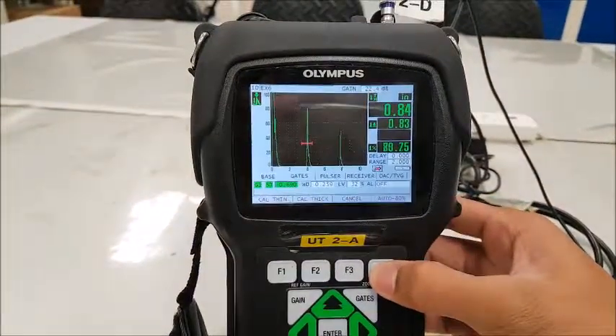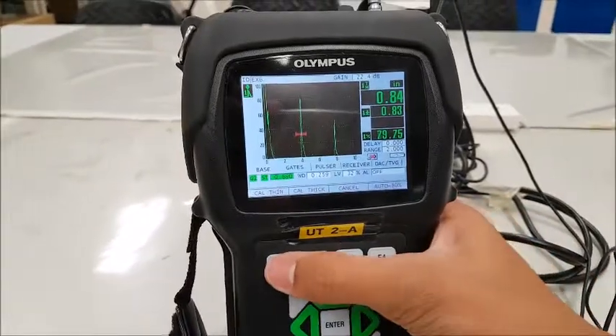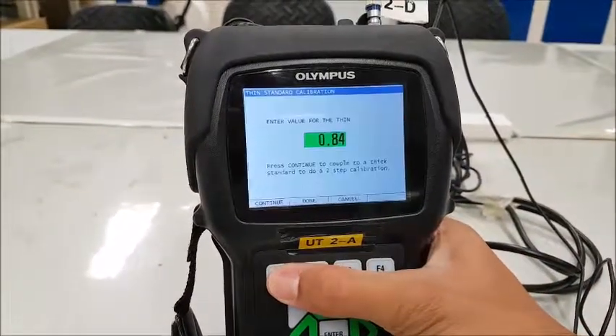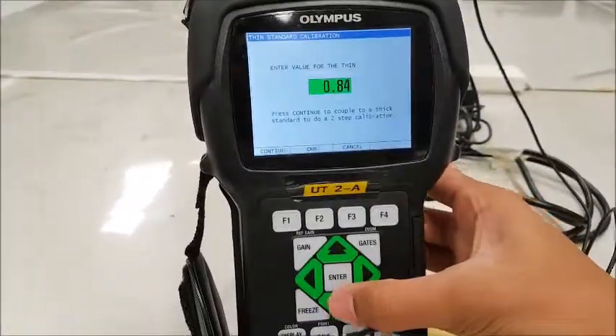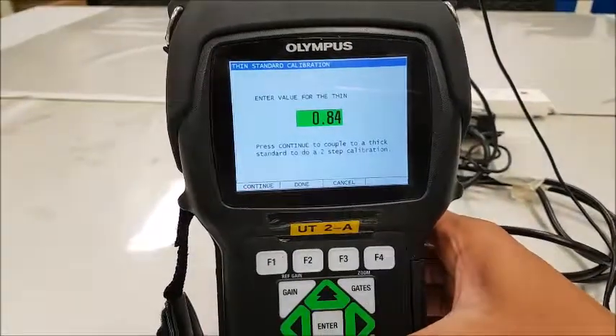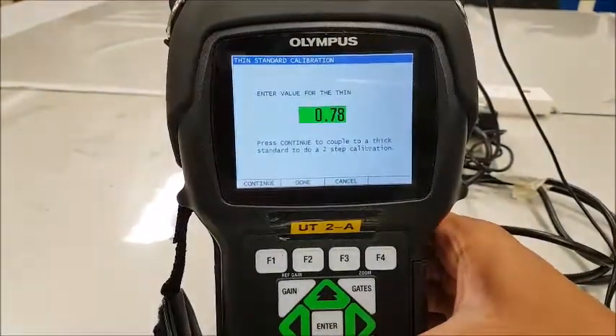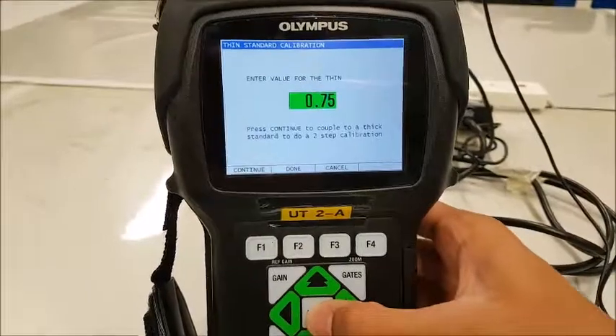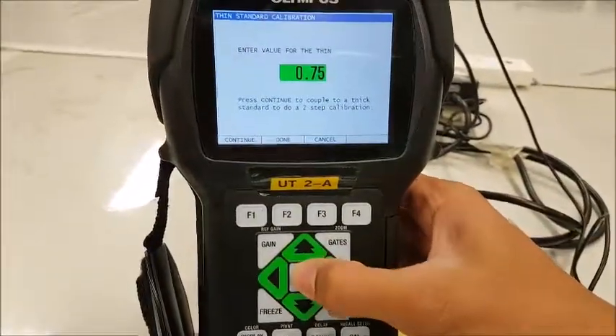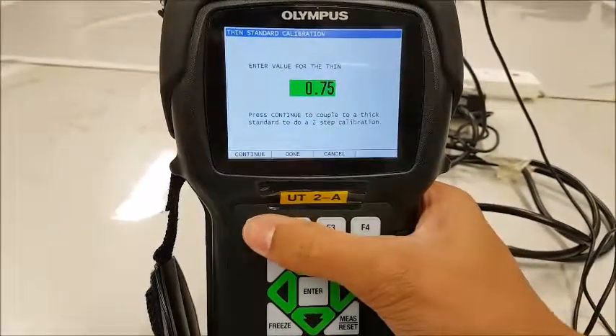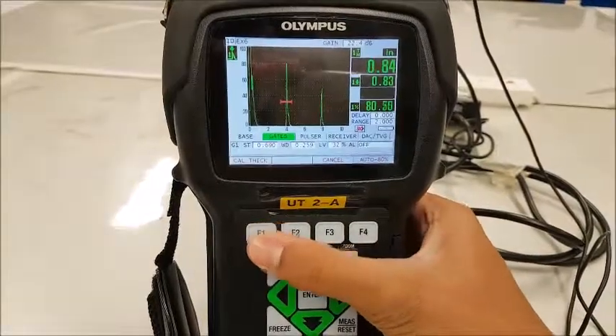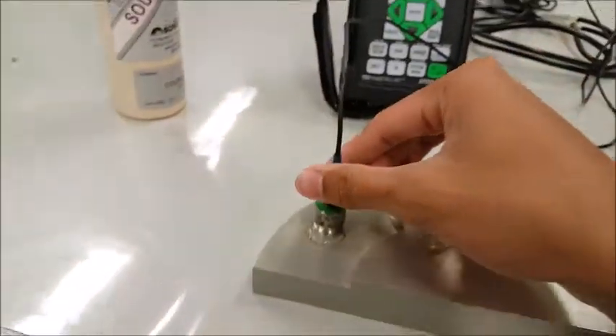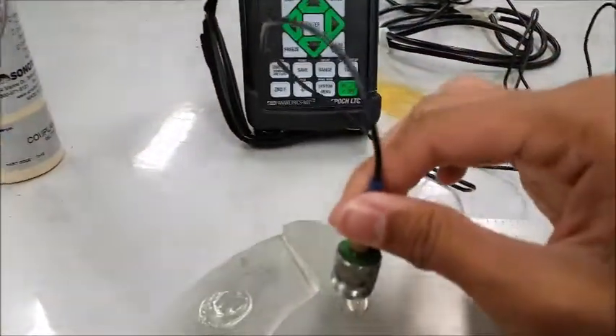Press F4, auto 80%, cal thin. A measurement, something like this will come out. Well, for a fact, I know it's 0.75 as mentioned. So you just want to press down all the way to 0.75. Press continue. Alright, so you can just take that off now. Put on the thicker one.